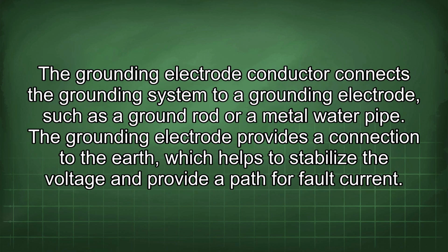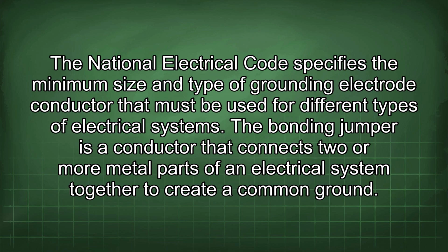The grounding electrode conductor connects the grounding system to a grounding electrode, such as a ground rod or a metal water pipe. The grounding electrode provides a connection to the earth, which helps to stabilize the voltage and provide a path for fault current. The National Electrical Code specifies the minimum size and type of grounding electrode conductor that must be used for different types of electrical systems.